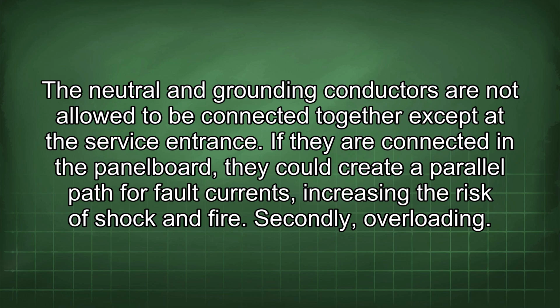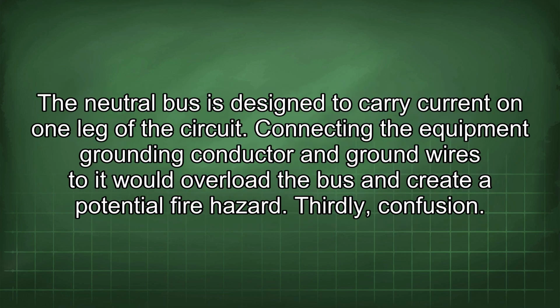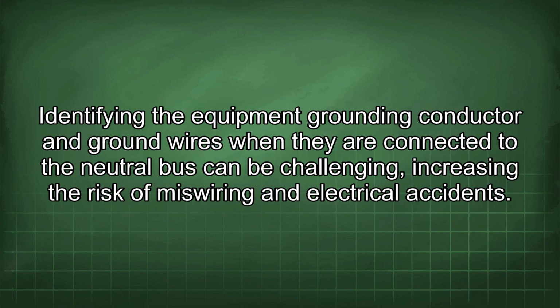If they are connected in the panel board, they could create a parallel path for fault currents, increasing the risk of shock and fire. Secondly, overloading. The neutral bus is designed to carry current on one leg of the circuit. Connecting the equipment grounding conductor and ground wires to it would overload the bus and create a potential fire hazard. Thirdly, confusion. Identifying the equipment grounding conductor and ground wires when they are connected to the neutral bus can be challenging, increasing the risk of miswiring and electrical accidents.